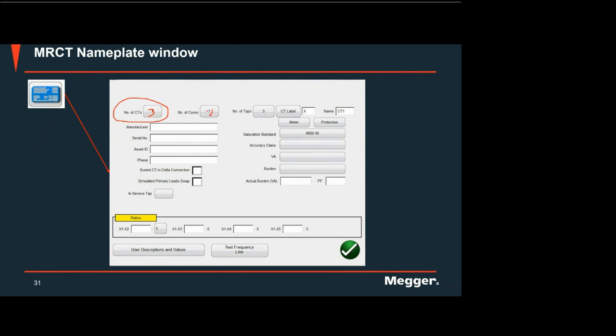The good thing with this one is that you can have one test form. You can have one test result for those 3 CTs. Unlike with the other equipment or the other brand, where you need to print a different test report for different CTs. So the good thing with this one, if your CTs are installed in the substation, is that you can have 3 results in one form. Not in one paper, but in one form.